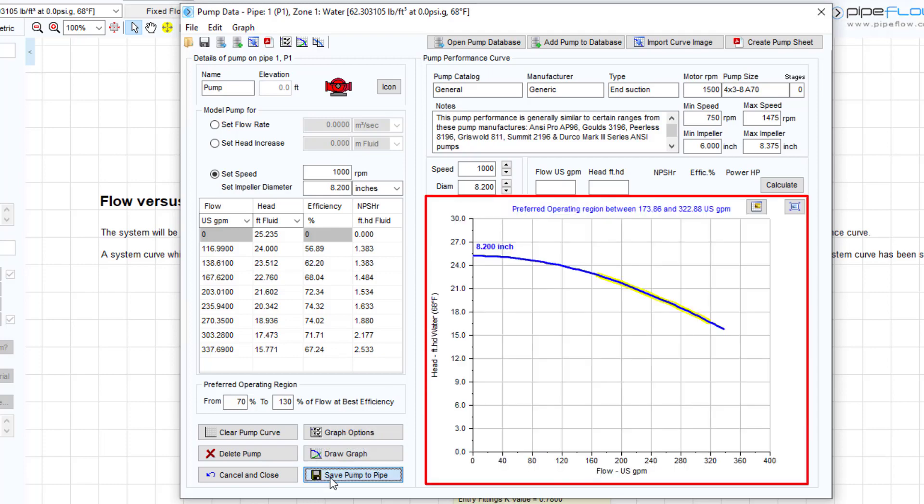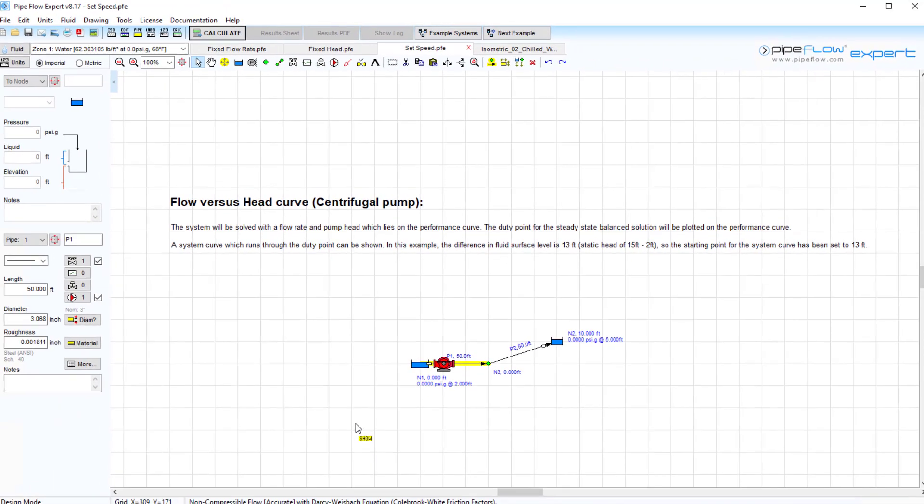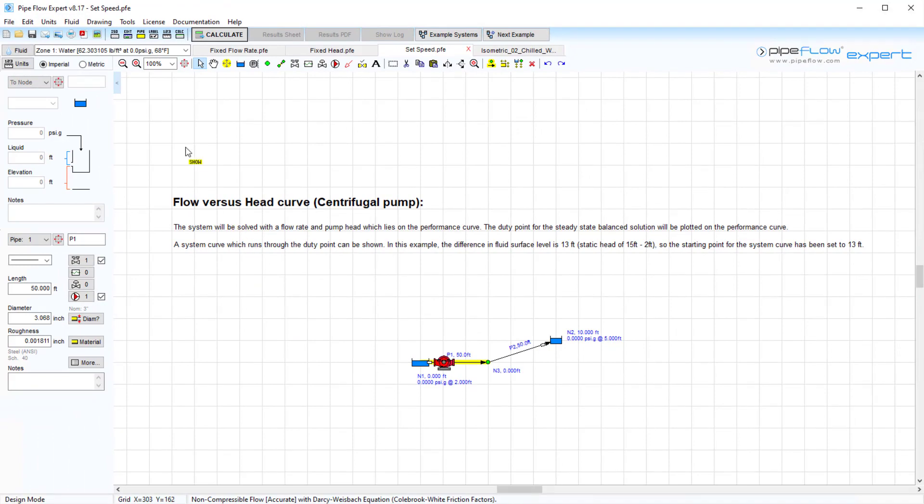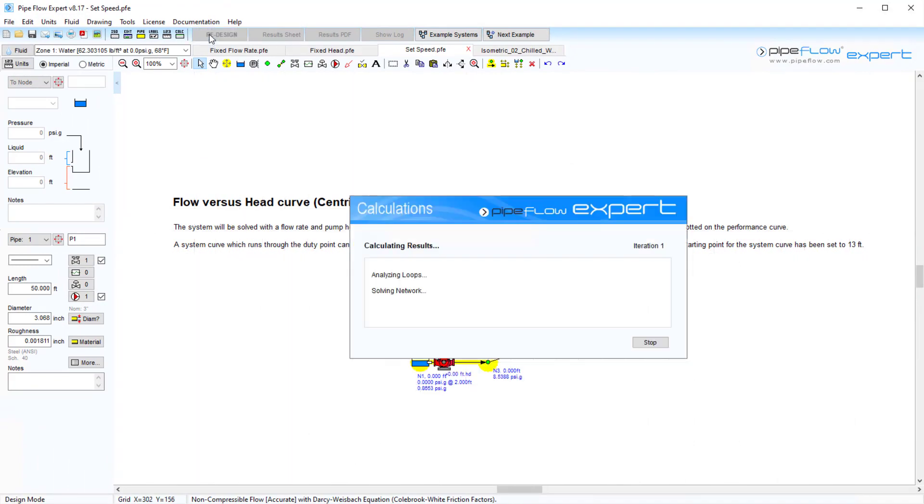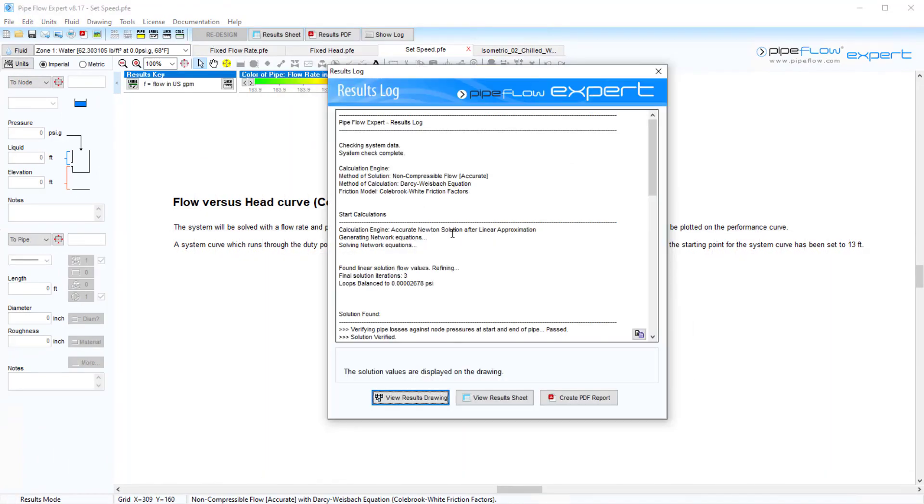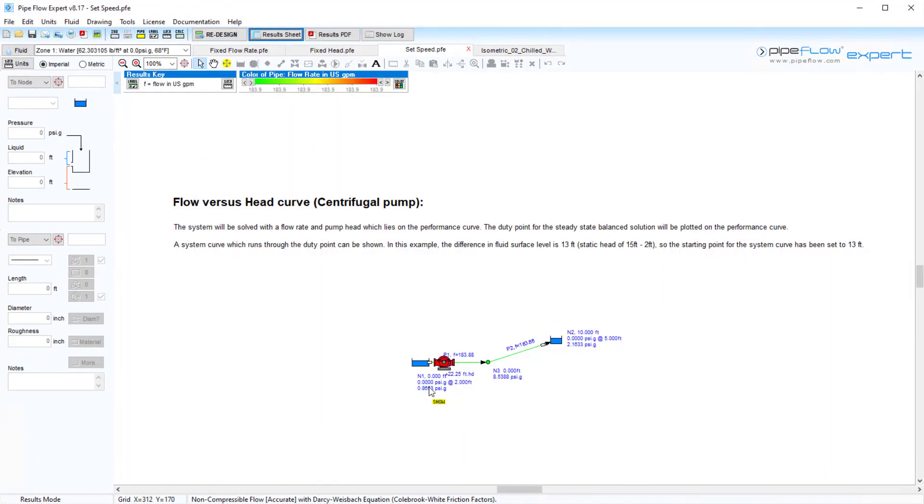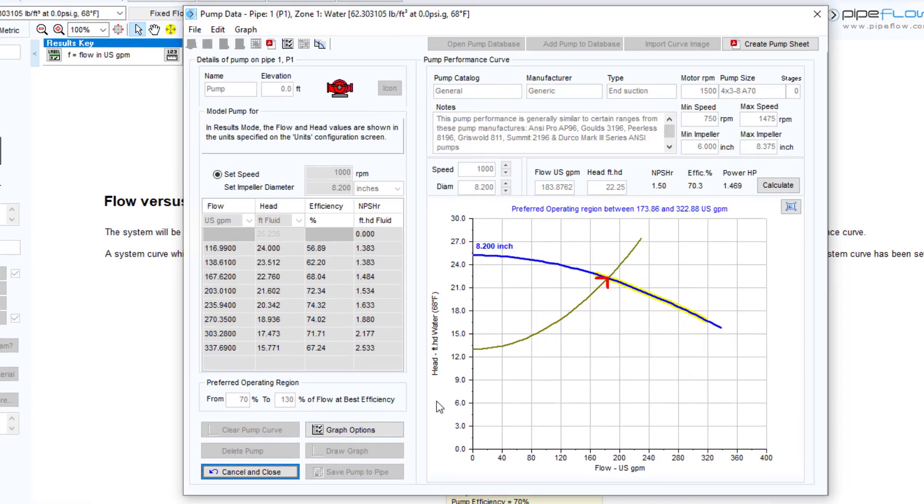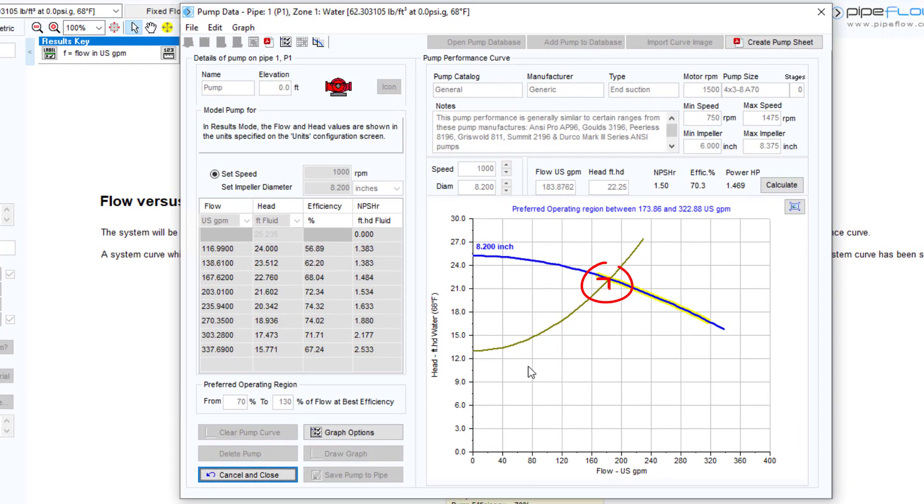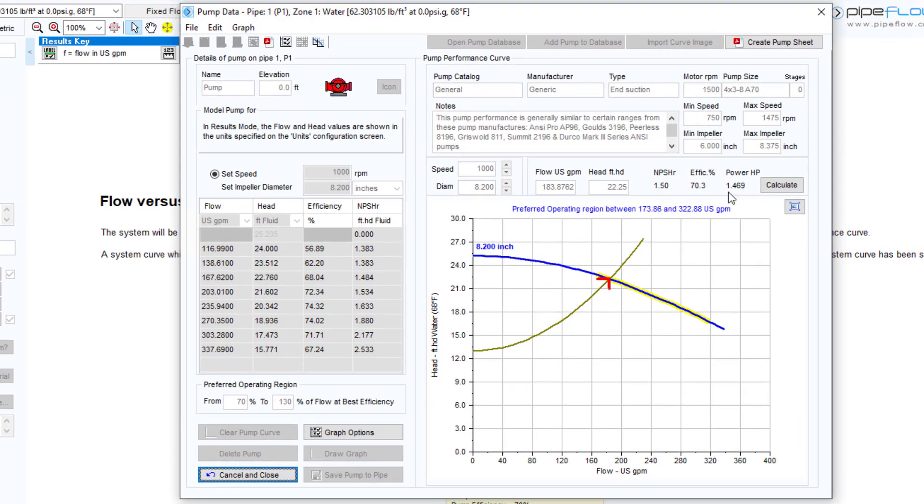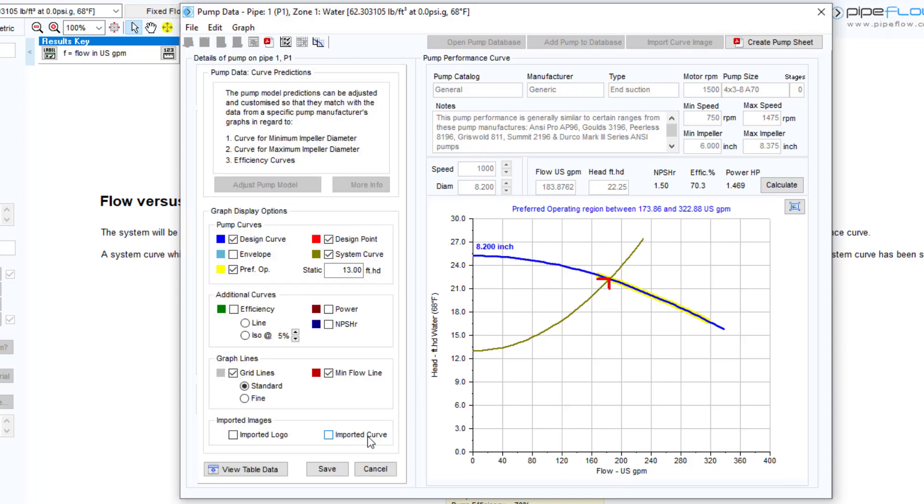The pump will produce a flow rate and a pump head to match the frictional resistance throughout the system. The duty point will be identified on the performance curve for the operating speed of the pump. More complex pump graph options can be produced which include speed and impeller diameter adjustments together with ISO lines to display an efficiency map for the pump.